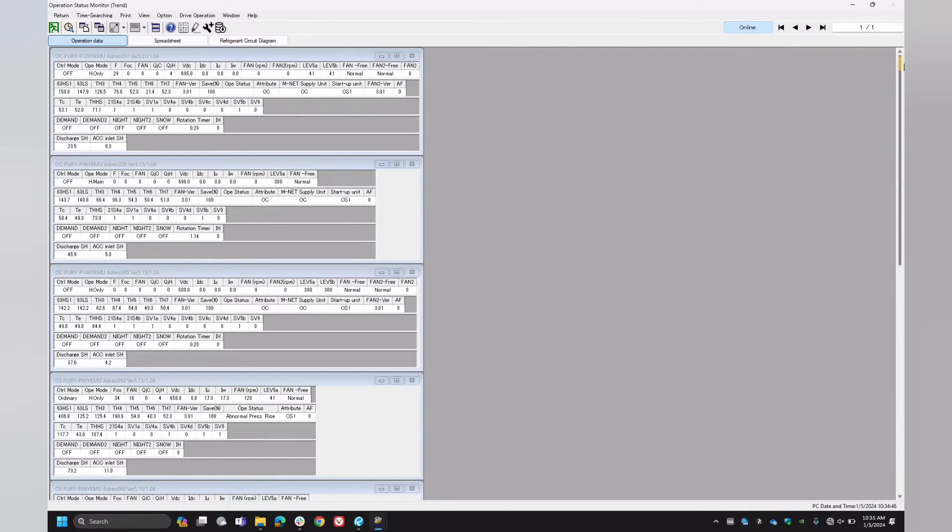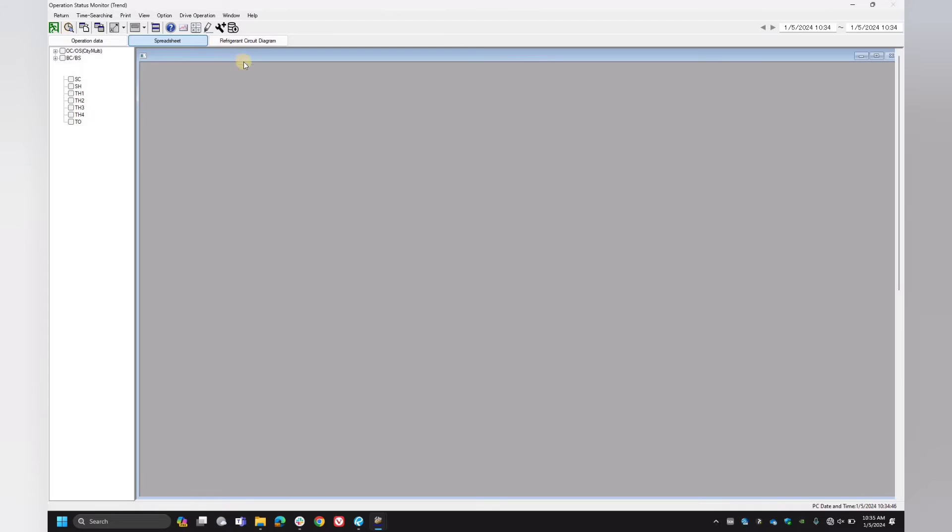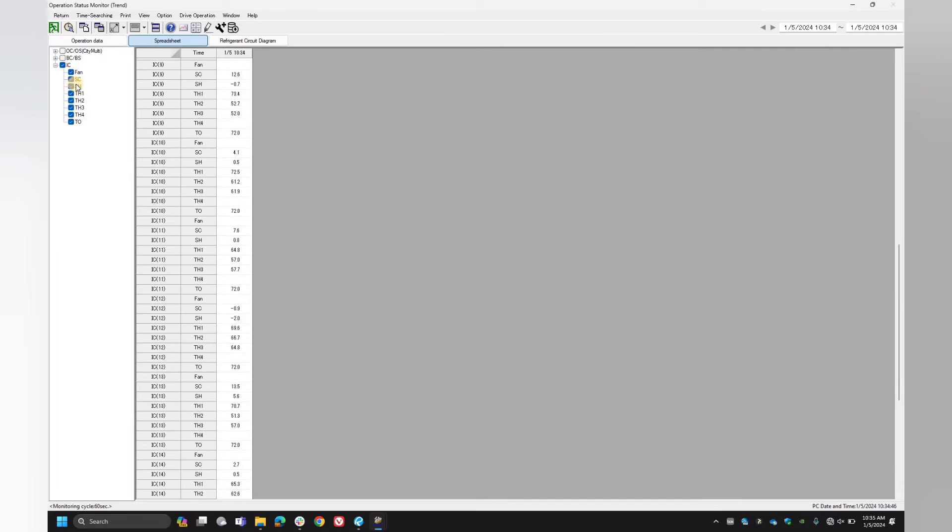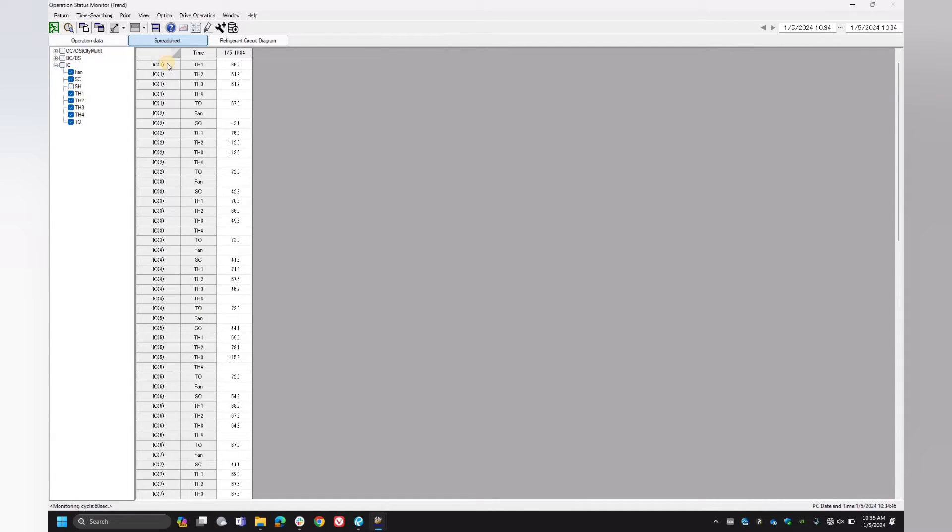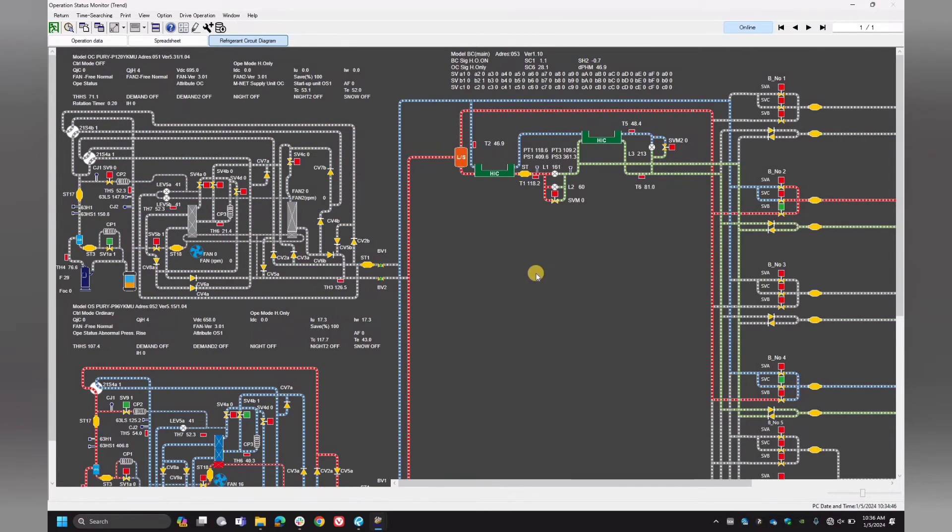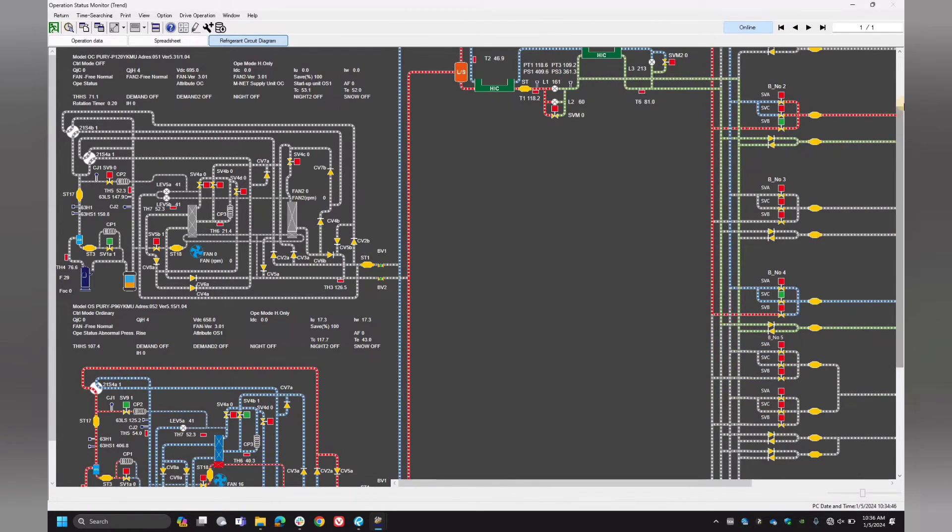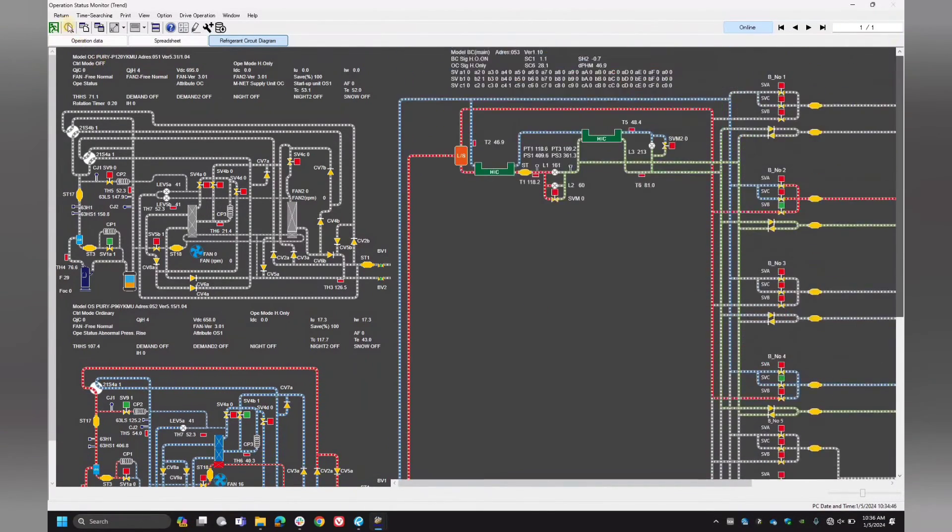Okay, so here's the report that it generated. You can expand this window here. And as now as you can see, you have all kinds of different information. You can break it down here by unit. So it shows you the current address of the unit here. You can also put it in a spreadsheet. And you can select everything here. And here it'll give you all the information here as you can see. It'll give you all of the different thermistor readings and fan speeds and all kinds of stuff here. You can also select here to view the refrigerant circuit diagram here. And this will show you a pretty cool diagram of your entire network here. So this is really nice to look at.